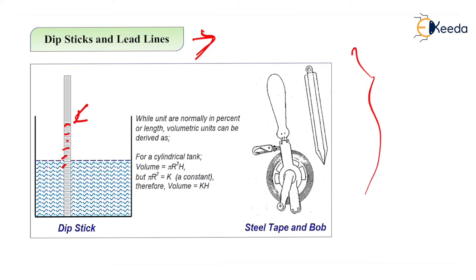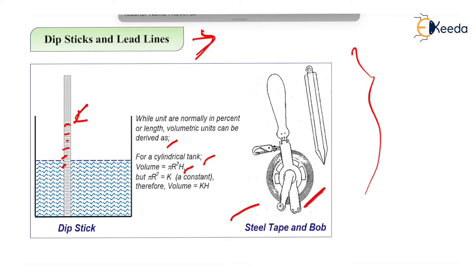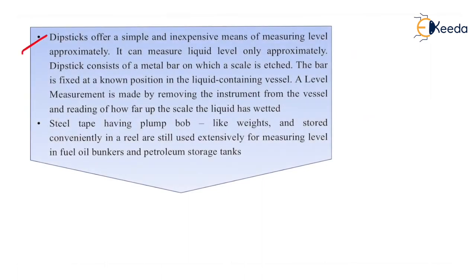Units are normally in percent or length; volumetric units can be derived for cylindrical tanks to measure volume. This shows the steel tape or bob type of liquid measurement. In this dipstick there are flexible lines fitted with an end weight. Lead lines have been used for centuries by seafaring men to gauge the depth of water under their ships. Steel tapes with plumb-bob-like weights, stored on a reel, are still used extensively for measuring fuel oil bunkers and petroleum level gauges. It offers a simple and inexpensive means of measuring level.